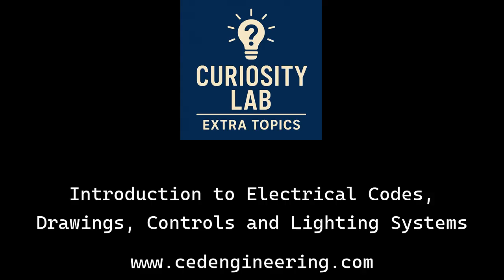First up, ampacity. We know it's the max current a wire can handle continuously, but the key thing is ampacity isn't fixed. It's not just about the wire size. It changes based on insulation type, the temperature around it, how many wires are bundled together in a pipe, a raceway. So you always have to check the NEC tables, especially in Article 310, and apply these derating rules if conditions aren't perfect. It stops the wires from overheating. Critically important.